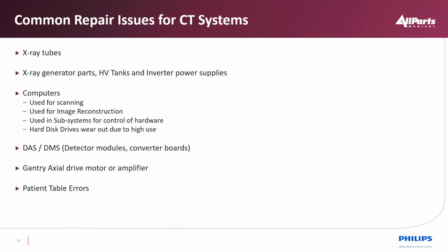But we'll still have X-ray generator parts, high voltage tanks, and inverters that drive the power the X-ray tubes utilize. In CT, 80,000 volts is typically the lower end, and then we go up to 140,000 volts. That's amazing how much energy we are putting through that X-ray tube to produce X-rays at an efficiency of only about 2%. Okay, but it's still useful, but we generate a lot of heat. So that heat, fans, all those things in the gantry, getting that heat out of the gantry is still very important, how we do it, either through water cooling or air cooling.